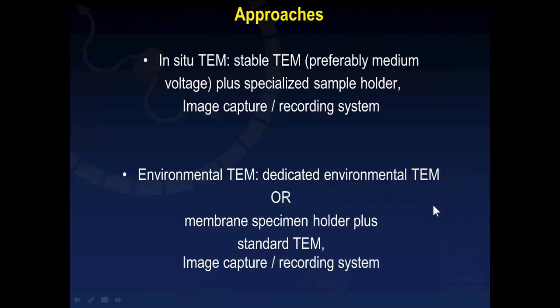The approach for in situ TEM includes a stable TEM — preferably a medium-voltage microscope — because with thin samples there is more structural detail and more quantitative information that can be resolved. One would also need a specialized sample holder as well as an image capture or recording system. For environmental TEM, one can utilize either a dedicated ETEM instrument or a membrane-based specimen holder, combined with a standard microscope and image capture system.